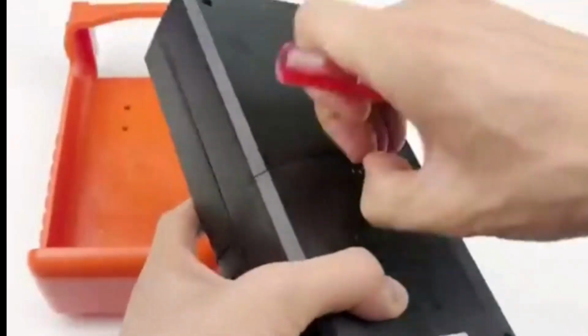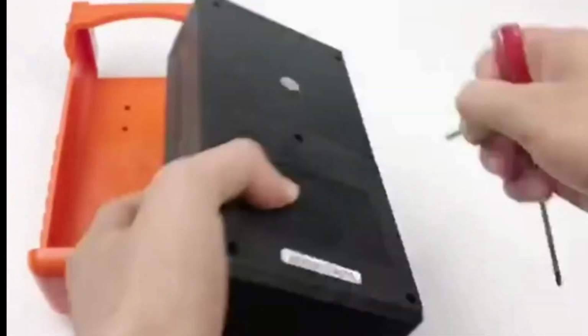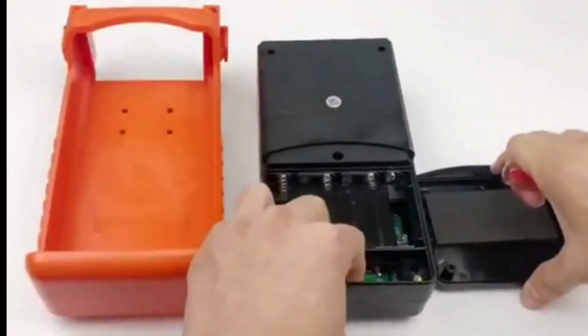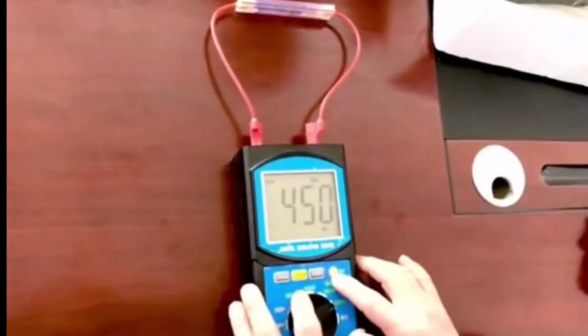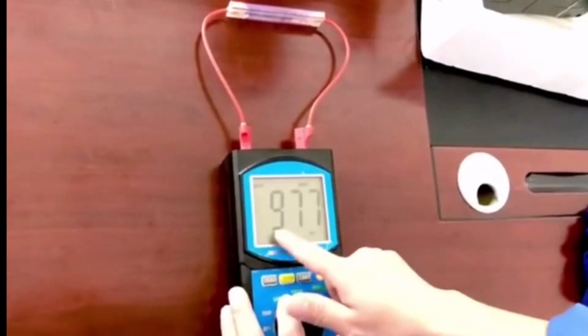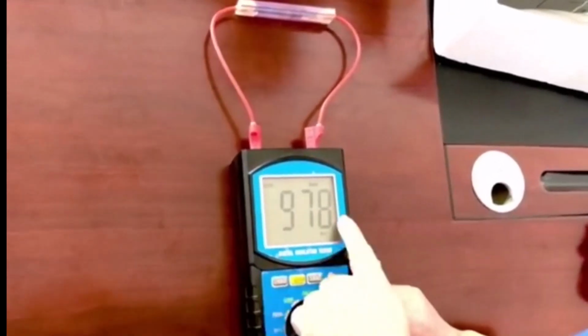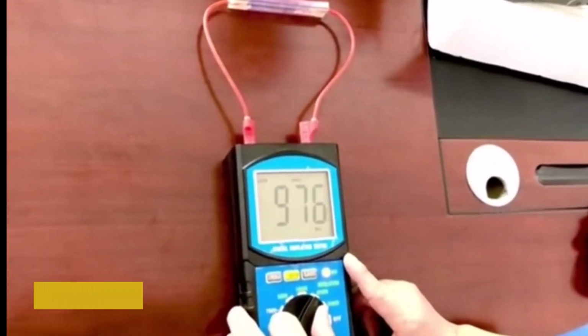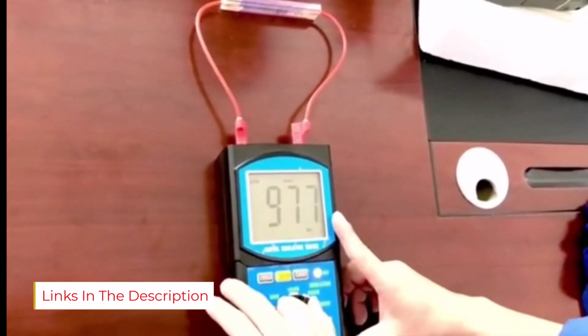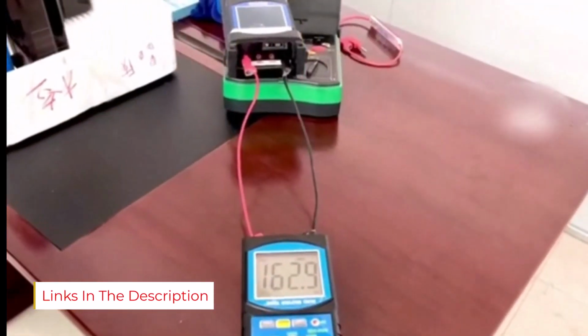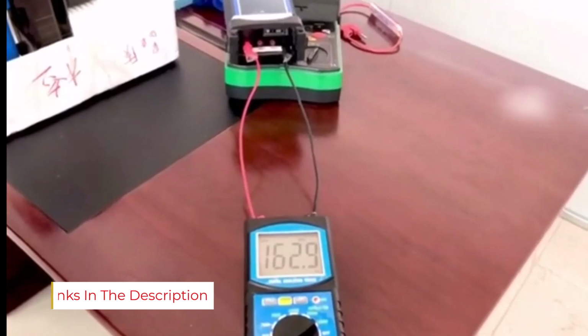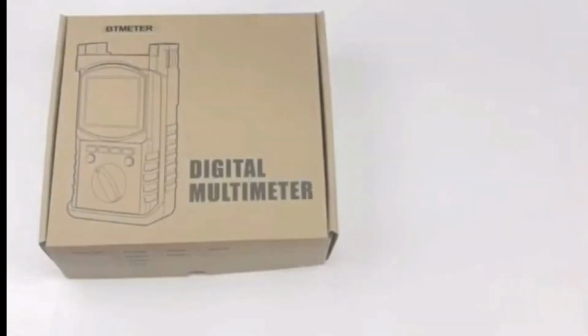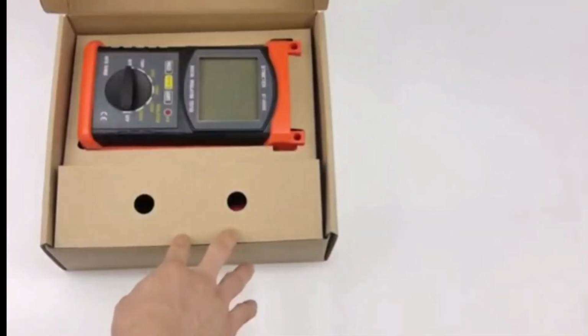And as for the testing capacity, you will find the BTMETER BT6688B compatible for a resistance range of 0.1 megohms to 200 gigohms. Even with such a high resistance capacity, the device maintains a pretty neat accuracy level of 3% to 10% plus 5 digits of the result. As for the voltage range, you will be able to use the BTMETER BT6688B at 100 volts to 5000 volts.